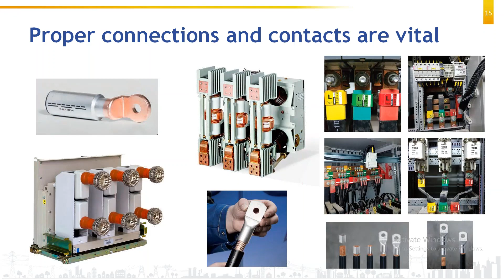See, this is one example taken of a circuit breaker. We discussed circuit breaker contact terminals, and we discussed this kind of nut and bolt connection. But there is one more kind of connection in the electrical system that is also susceptible to overheating. This is the jaw connection. This is the female part of the circuit breaker, and the male bus bar comes and enters into this. Because this is a movable connection which can be removed and entered multiple times, sometimes because of improper making of contact, this terminal also gets overheated. So this is one more application where we get quite significant overheating in certain places.